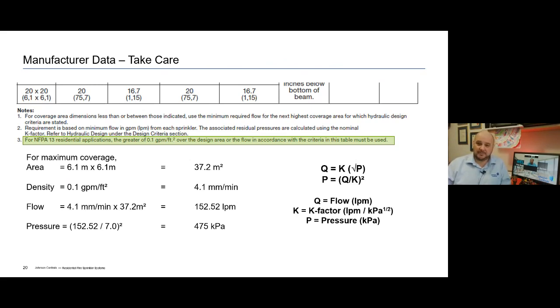So what a lot of people are doing is allowing for 115. We'll allow a little bit more, get 150 kilopascals, and that's how they're doing their design, to a very low pressure. But actually you need a lot more pressure. You need 3 times that because the pressure is under a square root, right? So it makes it even worse.